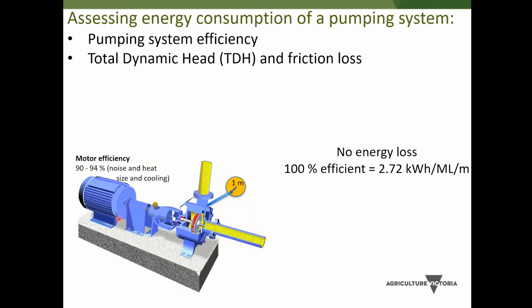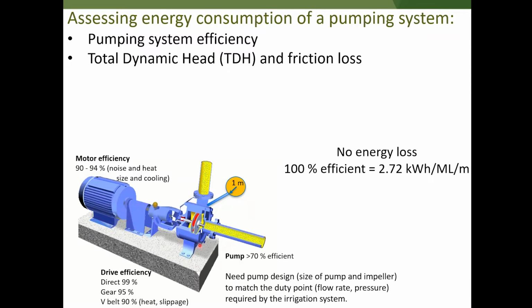There's efficiency losses in the motor, so we've got to size the motor right, and we've got to keep that well ventilated and cool. There's efficiency losses in the drive system, so direct shafts are quite efficient, but belts can slip and be fairly inefficient. And there's efficiency losses in the pump itself. And ideally, pumps will be better than 70% efficient.